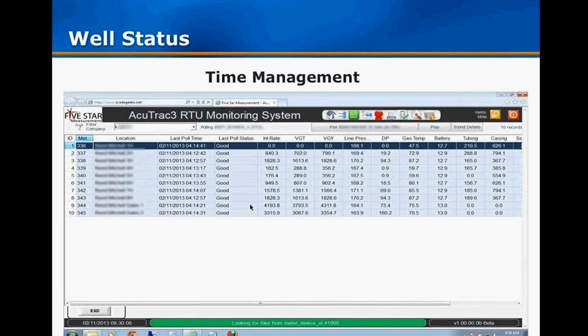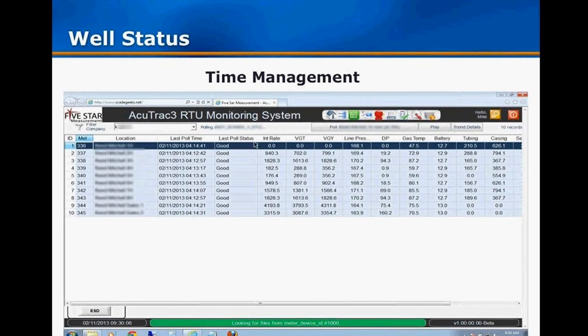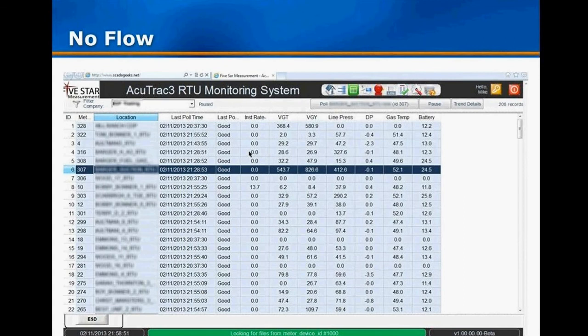Here's a screenshot of the well status screen. On this poll we got 'good.' Under battery, we see 12.9 and 12.7 — everything looks good there. Volume gas today (VGT) and volume gas yesterday (VGY) are shown, along with line pressure or static pressure, differential pressure, temperature, gas temperature, tubing and casing. The no-flow slide shows instant rate coming back as zeros, meaning no flow on those meters. Engineers can sort this and prioritize those wells to get them back online.